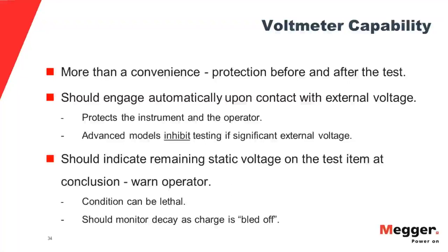But at the end of the test, you also want to de-energize the test item. The tester is not dangerous. The test item can be, because you can store a large static voltage in the construction of the thing that you're testing. A big motor winding, a long run of cable has a lot of capacitance in it.